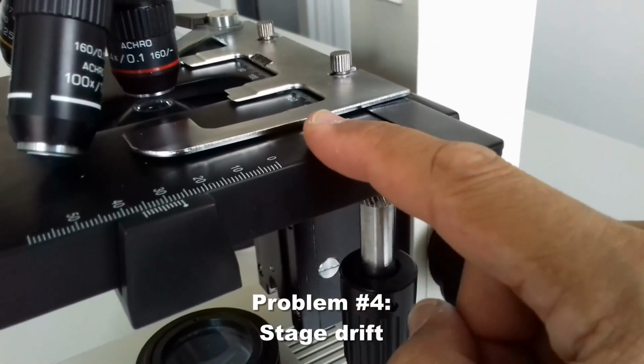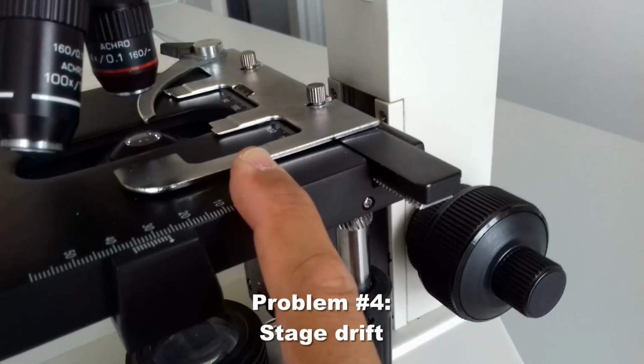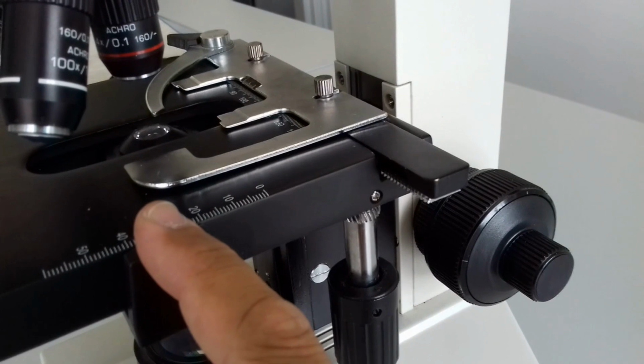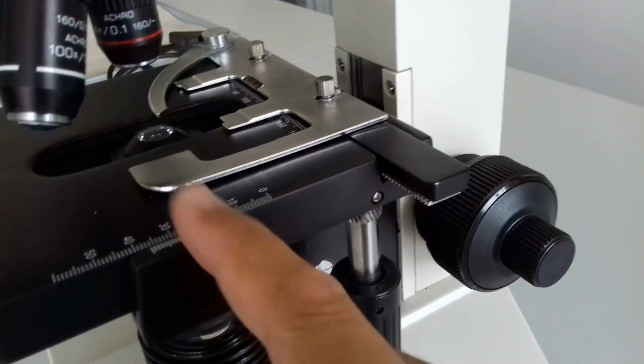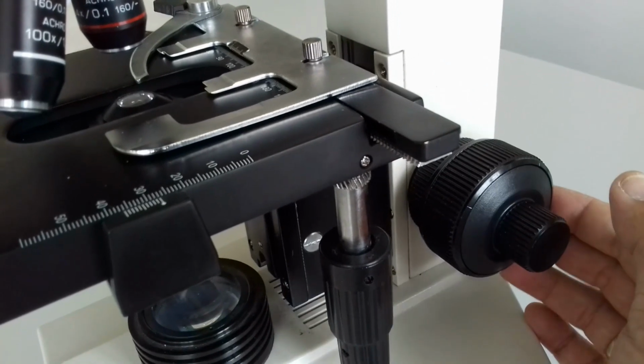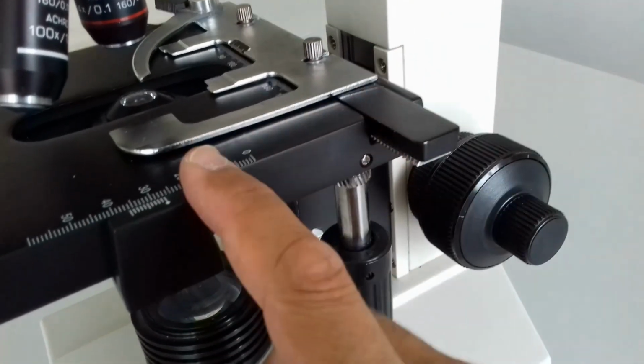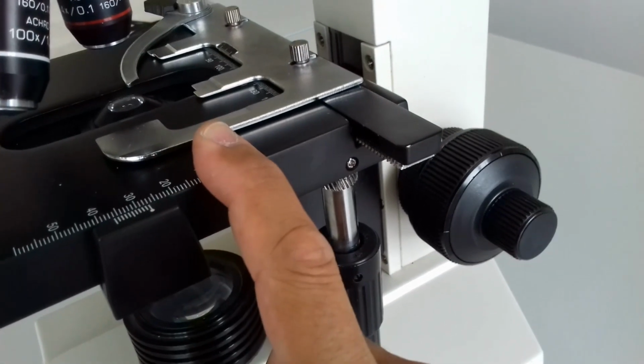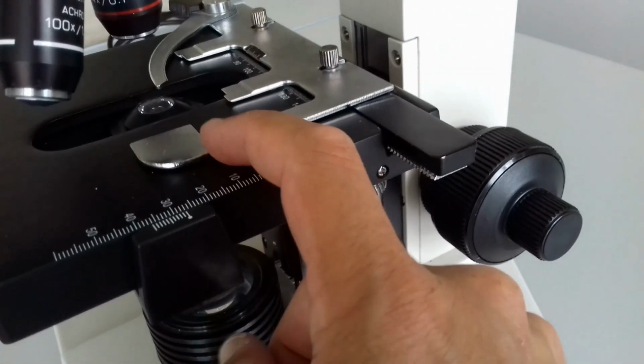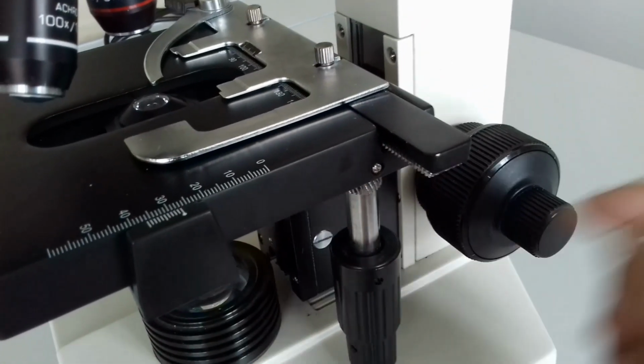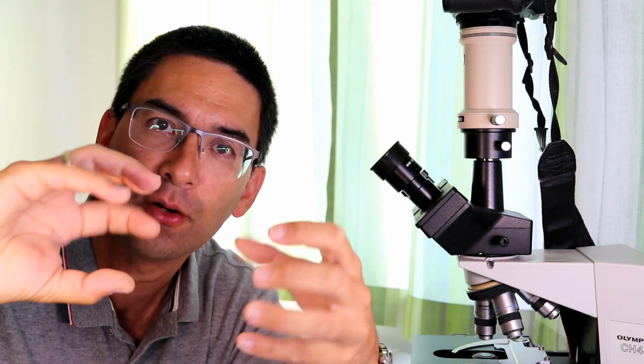Stage drift is, strictly speaking, not something unusual. Stage drift happens when the stage of the microscope drops down, either on its own or if you apply a light pressure. This can easily be adjusted by turning a tightening screw, which can be found where the coarse focus is. Some other microscopes allow you to do this by turning the two coarse focus knobs against each other in opposing directions, and this also tightens it. So it's not really a problem, or should not be a problem, but I tried to do this on the microscope, and then something snapped and it broke. It physically broke.